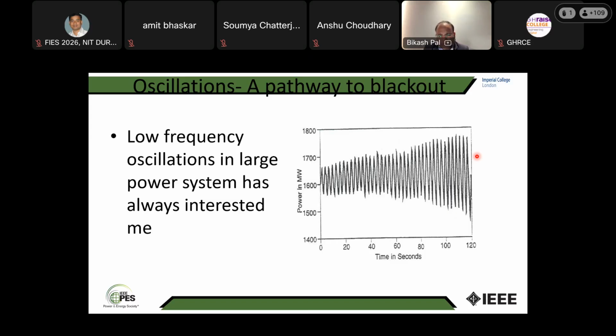Many blackouts have happened historically, from 1969 to as recent as even 2025. The blackout in Spain in the month of April was because of the oscillation in the transmission circuit. You could see that power is thousands of megawatts, and there's a very low frequency oscillation of about 0.5. So this is the context for how we then dampen this oscillation. Dampening of the oscillations can be done through control.